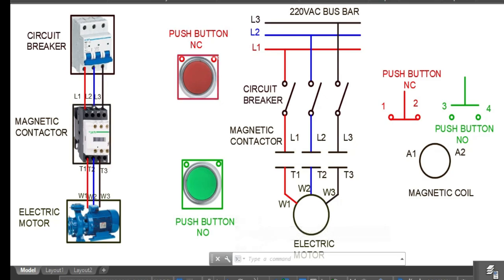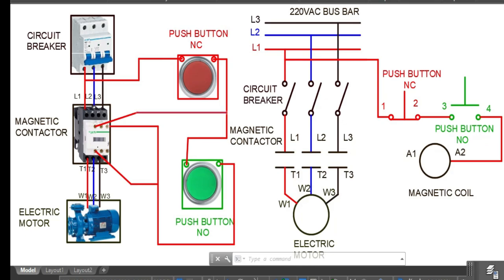Now I need to make the wiring for the auxiliary contact, for the push buttons. Now I make the wiring for the normally closed push button. You can see here there's already the push button. This is from line 1 going to the stop push button normally closed, the out going to the normally open push button, and then out of the normally open push button is going to the magnetic contactor coil, A1. Then A2, I need to make the wiring for A2.